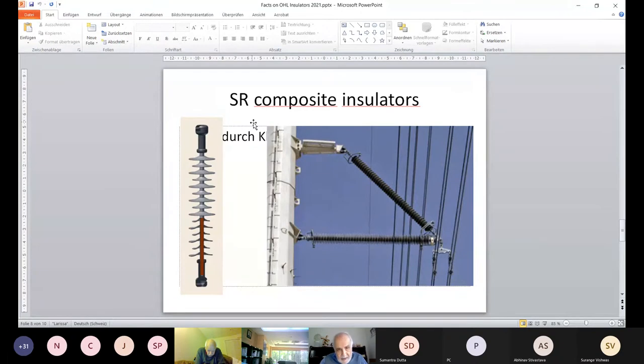There are some applications, that's why I put this picture here. Some applications like compact lines with so-called horizontal V insulating cross arms are only possible for high voltages. This is a 400 kV example, only possible with composite insulators because of their specific properties, which are flexibility, so they can take better compression loads than the other materials.